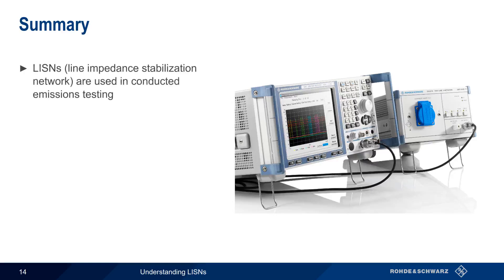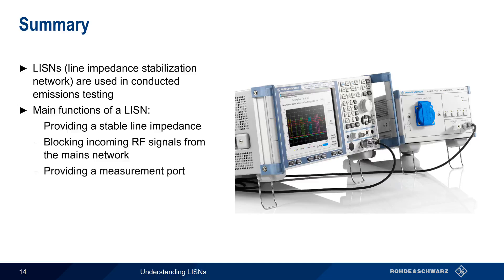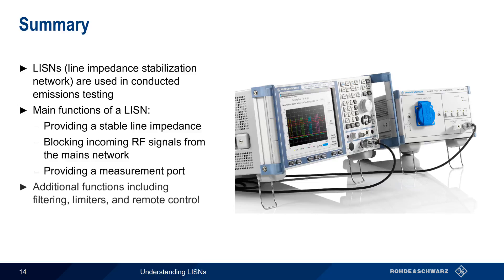In summary, a LISN, or Line Impedance Stabilization Network, is used in conducted EMC emissions testing. A LISN provides three main functions. First, as the name implies, it provides a stable line impedance for the equipment under test, which greatly improves the repeatability of results between different test locations. A LISN also blocks incoming RF signals, to ensure that we're measuring emissions from the EUT and not signals conducted in over the mains network. And finally, a LISN provides a measurement port for attaching test equipment, such as an EMI receiver, spectrum analyzer, or oscilloscope. Some LISNs also provide additional functions such as filtering, limiters, and the ability to control the LISN remotely. This concludes our presentation, Understanding LISNs. Thanks for watching.